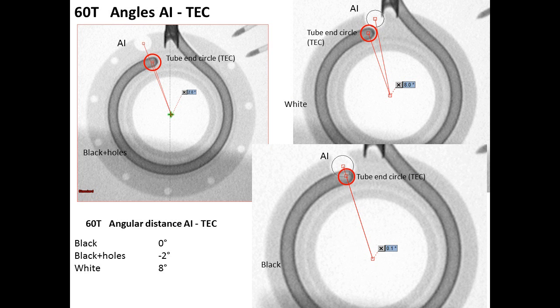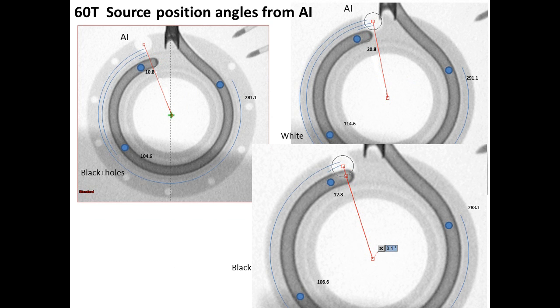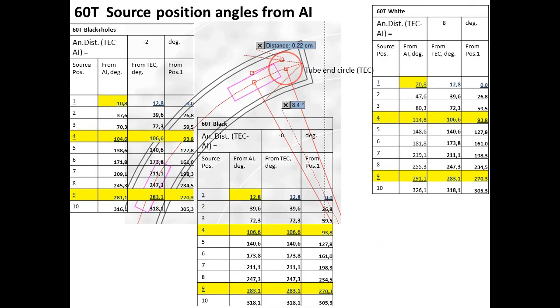From the fluoroscopic part of applicator commissioning, we measure relative angles between the angular indicator and the center of the titanium tube tip. Here we name it as tube end circle, which we use in film testing as a reference angle. This way we know angular positions of the radiation source relative to the angular indicator, just what we need for applicator reconstruction in the treatment planning procedure, or in table numerical representation.